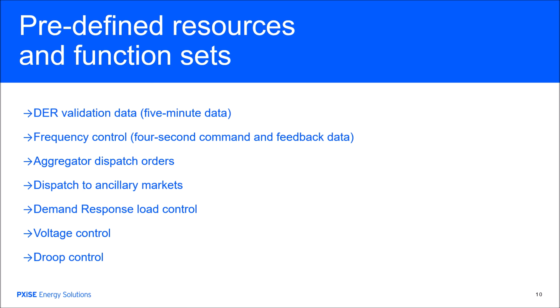This is a typical example of what they call an energy resources function set. I want to take a minute to describe the chart on the right. Many companies do have issues with the sign of power — is positive power going into the DER or is it coming out of the DER? The same way with reactive power. This standard specifically defines the 4-quadrant inverter.